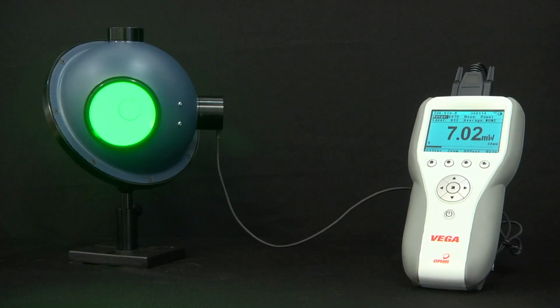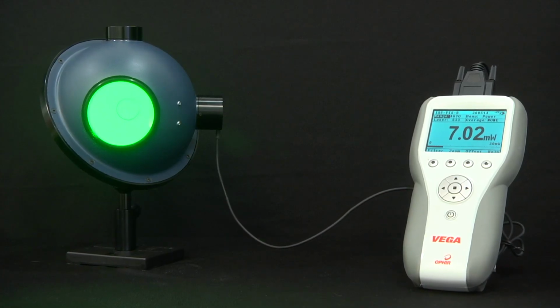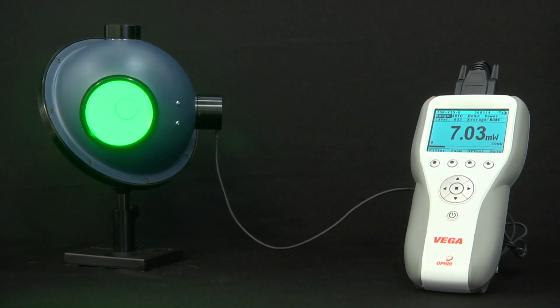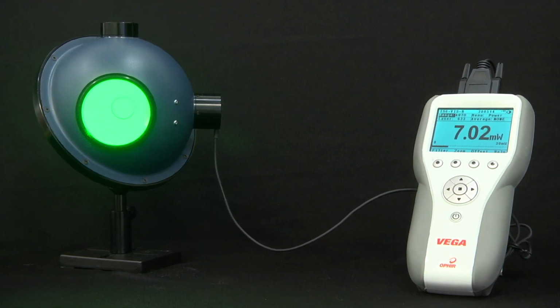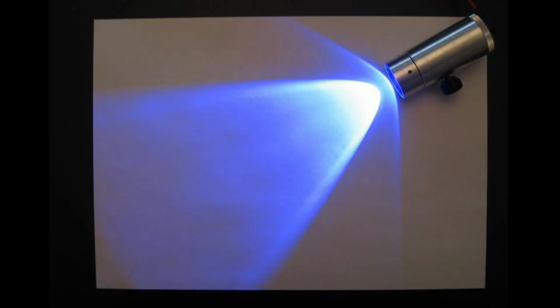If your application requires measurement of a widely diverging beam, an integrating sphere might be the right solution. An integrating sphere is an optical component that captures a light beam and enables you to measure the power in the beam under conditions that would otherwise be very challenging. For example, a widely diverging beam that might overfill a regular sensor's aperture.